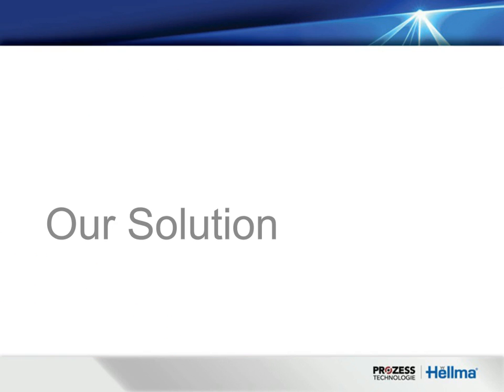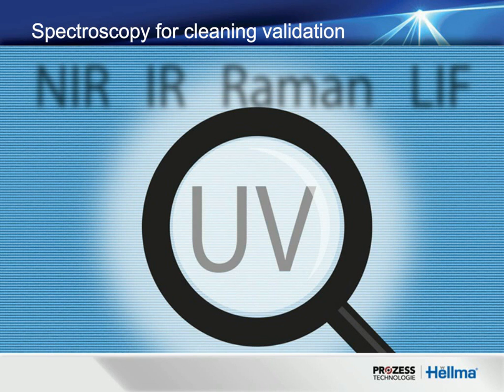So we're going to talk a little bit about our solution, and I'm going to start talking about the process aspect of this solution before Evan picks up and talks a little bit about Helma's contribution to the solution as well. So we're talking about UV spectroscopy today. While there are a number of optical spectroscopies that can be and have been applied for cleaning or a variety of other process approaches, UV is well suited. Near infrared can be used, but the detection limits are relatively high compared to UV. There you're talking about percent level or fractional percent, which typically will not allow you to validate a cleaning process.